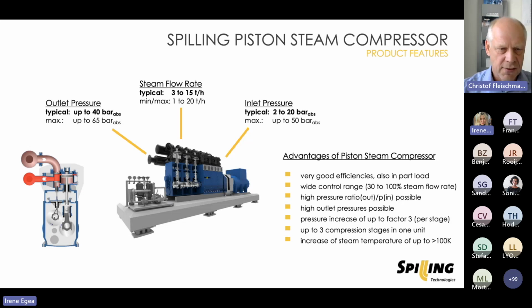Now, the advantages of such piston machines is simply their good efficiency, not only at the full load operation, but also in part load operation. So these machines are also very flexible. We can throttle them down to 30% flow rate. And in the complete regulation range between 30 and 100% flow rate through the machine, they have always the same efficiency. And so also the electrical power consumption is really proportional to the steam flow rate, meaning when you have 50% flow rate, the machine also consumes only about 50% electrical power.